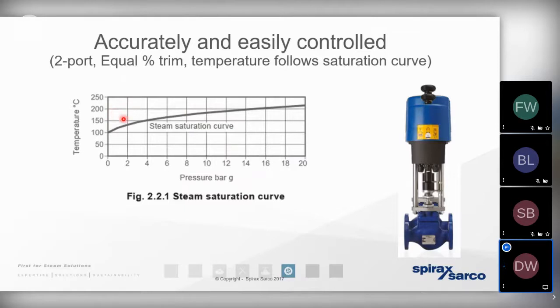And once we've reduced the pressure of the steam at the process down to 2 bar gauge, 132 degrees, the condensate will exist at the same conditions. It's a different phase, it's a different state, but it will exist with the same pressure temperature relationship. There's just simply far, far less energy contained within it.